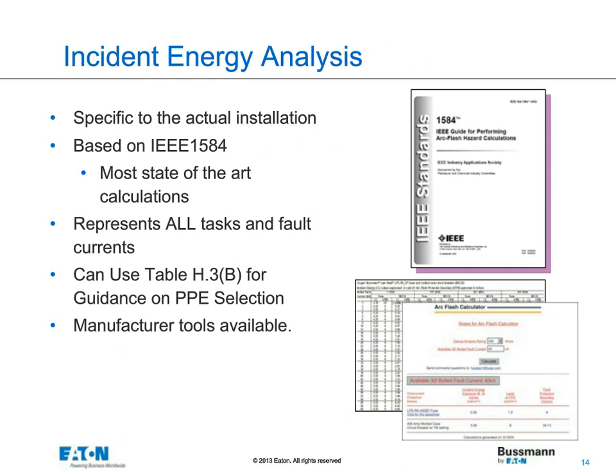When it comes to doing an analysis method, most companies that offer this service are going to use the IEEE 1584 method. It represents all tasks and all fault currents. So what you'll see with the table method is that you might actually dress for a lower hazard if the task is less likely to result in an arc flash. In this case, when we do the analysis method, we calculate the worst case, and so regardless of task, it identifies the worst case arcing hazard and doesn't factor into consideration the risk, if you will, of an arc flash hazard.